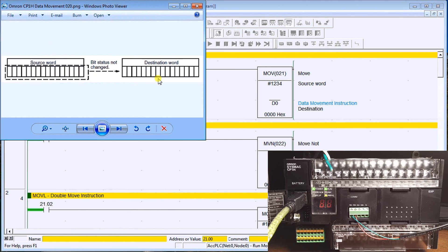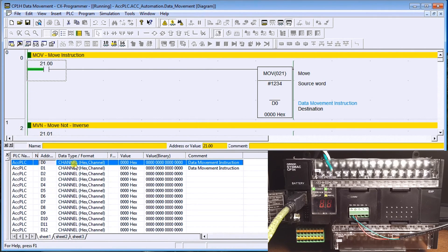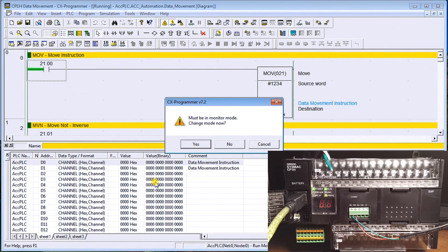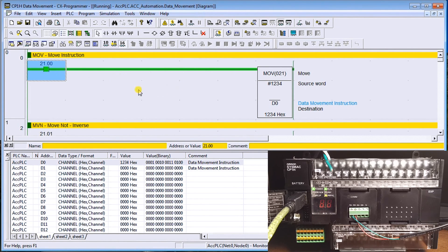We're taking the source word and moving it to the destination. Looking at the data, data memory zero currently contains the value zero. We switch to monitor mode and turn it on — now the number 1234 goes into data memory zero. You can see the value in hex and in the individual bits of that channel. Data movement just moves bits of information, whether a word or a bit, into another location.